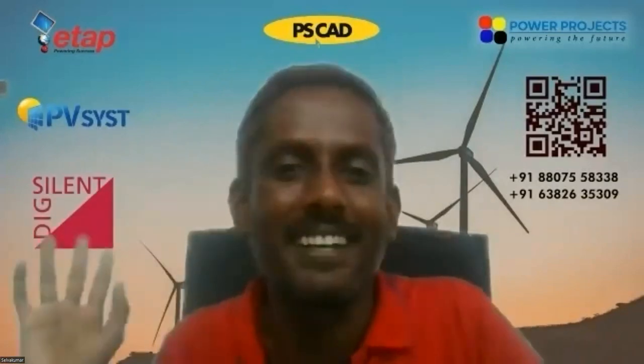Probably you'd say an arc flash study is needed for harmonic quality, etc. I'm not really denying the requirement of an arc flash study. It should not be understood from that aspect. We have performed 20 arc flash studies, and in 95% of the cases the customer has approached us saying, sir, we need to perform an arc flash study. I am asking the question, why? That's as simple as that. If I ask for relay settings, we will not get them. If I ask for transformer impedance, we will not get it. If I ask for cable length, we will not get it. But they need a document called an arc flash report.